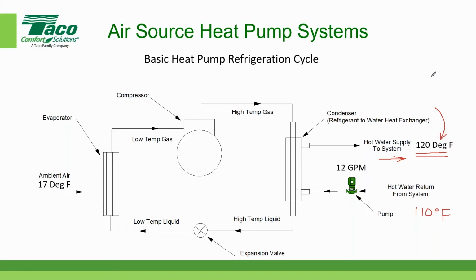And again, repeating, the terminal device like a fan coil or some other device that's used to heat the building would operate at an entering water temperature of 120 degrees. Now, certainly with radiant floor heating systems, they can easily operate between 100 and 110 degrees. So these work nicely with those types of systems also.